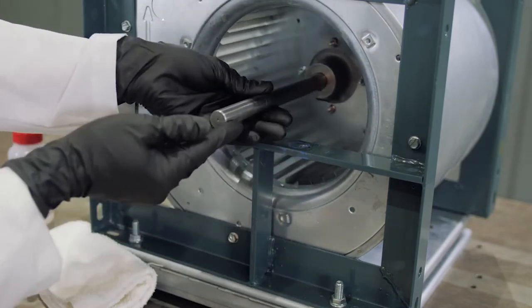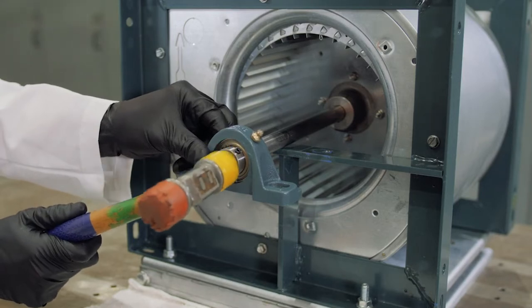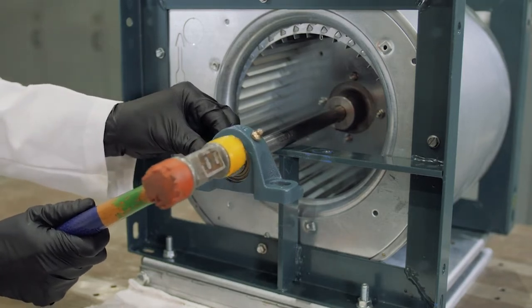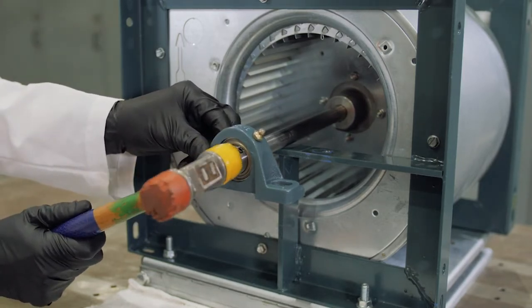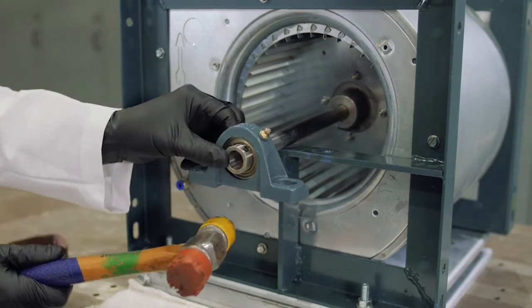Clean the shaft as needed. Slip the bearing into the desired position. For tighter fits, tap the face of the inner ring with a soft driver. Do not strike the housing as this may damage the bearing.